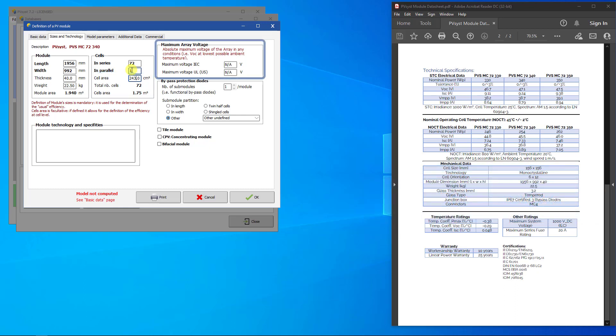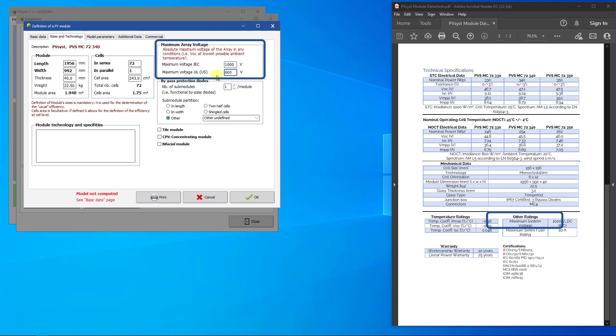For the maximum array voltage, the IEC value is usually 1,000 volts for standard PV modules. Nowadays, more and more modules are specified for 1,500 volts to be used in high-voltage PV systems. In the United States, some modules are specified for 600 volts due to special regulation rules for electrical systems.